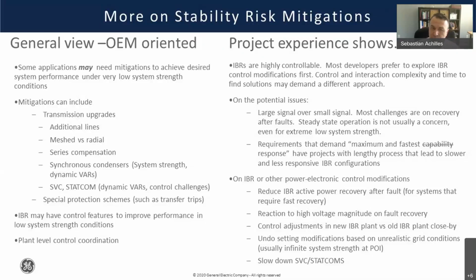The next point is related to requirements that demand maximum and fastest response. I purposely left "capability" scratched because I think the industry sometimes confuses asking for what is possible, what this equipment is capable of, with demanding that it be implemented in the project. There are several systems where the maximum and fastest response is demanded to get the project connected. Then when you connect it, or study it in more detail, you realize that you need less responsive or slower equipment. Otherwise, you get bulk power system type instabilities through the interaction with the grid. This issue is fairly common, at least globally.